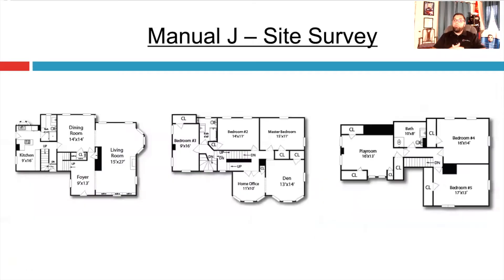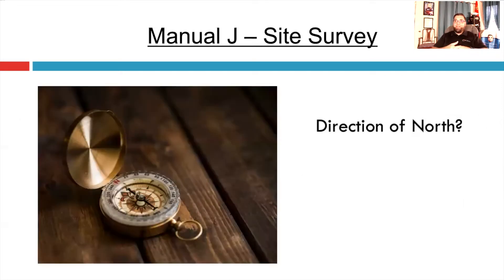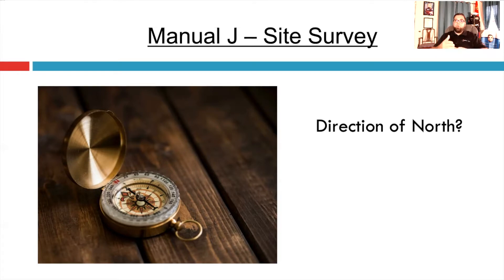If you're doing a room-by-room load calculation, having the zone-by-zone or room-by-room breakout will really help you identify if you missed any windows or significant outside walls for that room. Make sure you have that floor plan available. One thing I always forgot was the direction of north — I would always verify that with Google Maps and orient it with the front door, so I knew which way all of those windows and everything faced on my floor plan.